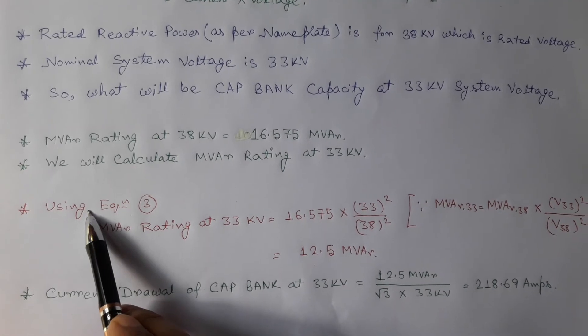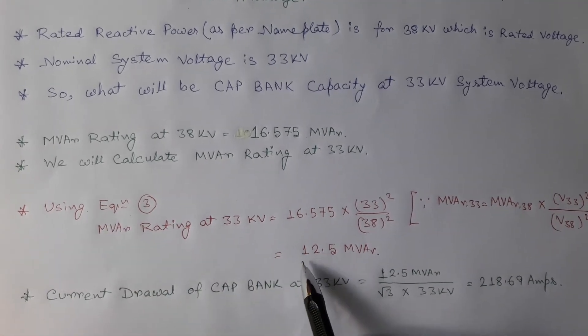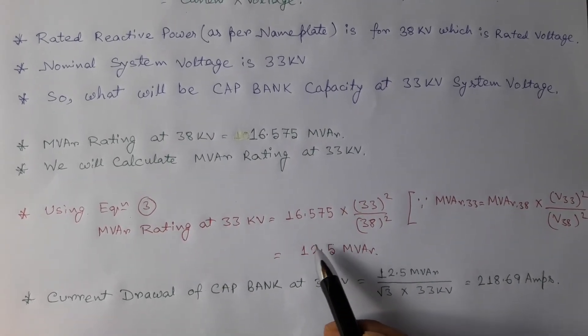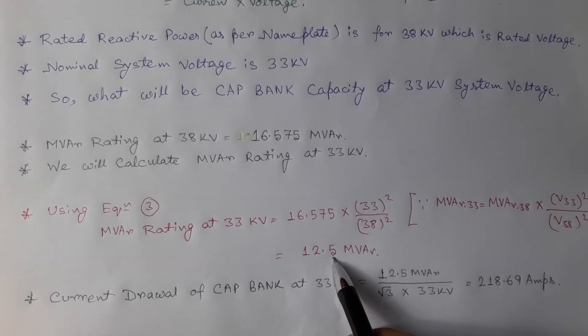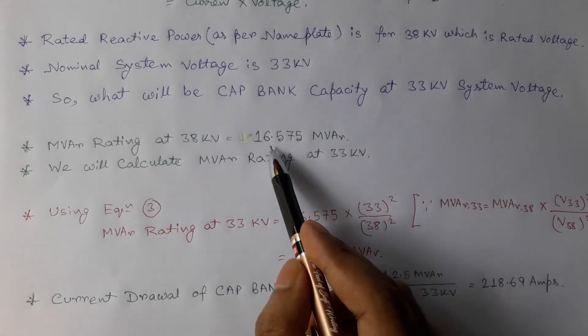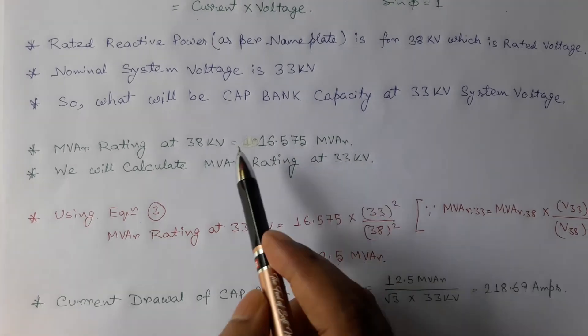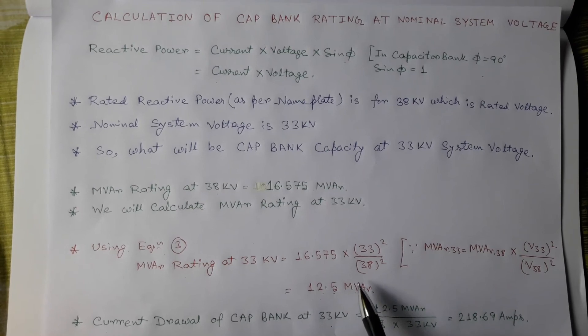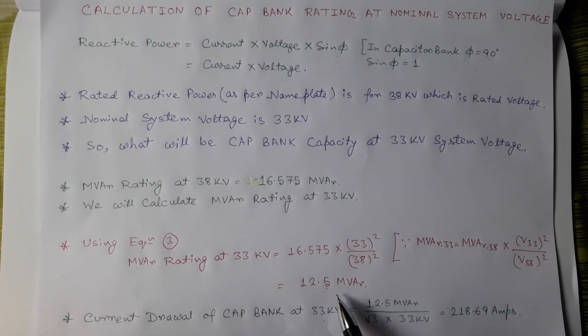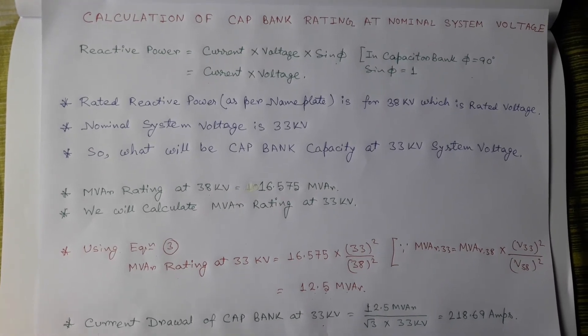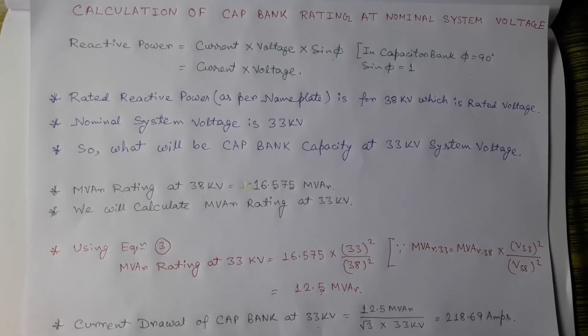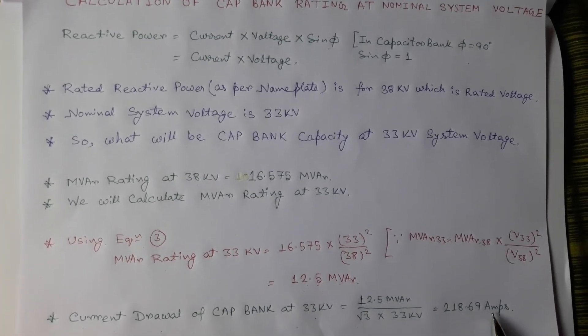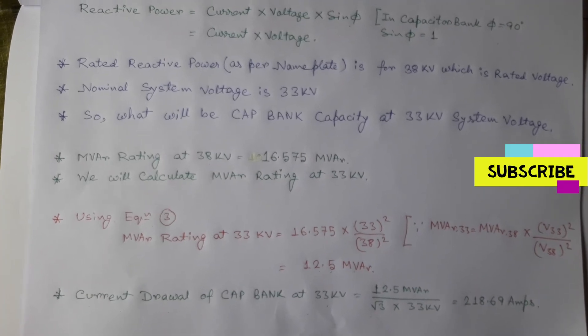Using equation 3, the reactive power or mVar rating of the capacitor bank at 33 kV is calculated to be 12.5 mVar. Using this calculated reactive power rating at 33 kV, we can also determine the current through the capacitor bank at 33 kV, which is 218 amperes in this case.